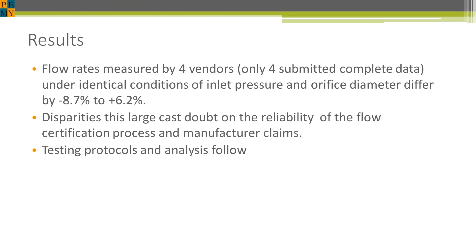The overall test program results are displayed here. There are large discrepancies in the flow rates measured by the vendors on fixed orifices. The flow certification process in API 2000 as it stands may not be credible. Details about the study follow next.